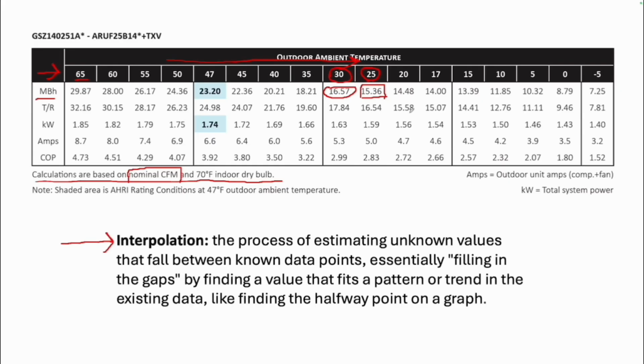You have to take a moment and read through the documents, but imagine you being an end user questioning whether the system's running correctly, and a technician comes out and says, well, it looks like it's running fine to me. They're not necessarily going to be happy with that. But what if the technician says, I have first off measured your airflow, and then I used that information and was able to compute the delivered capacity of your system right now as it's running.